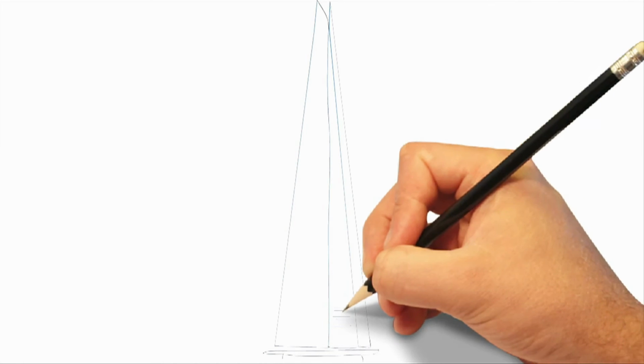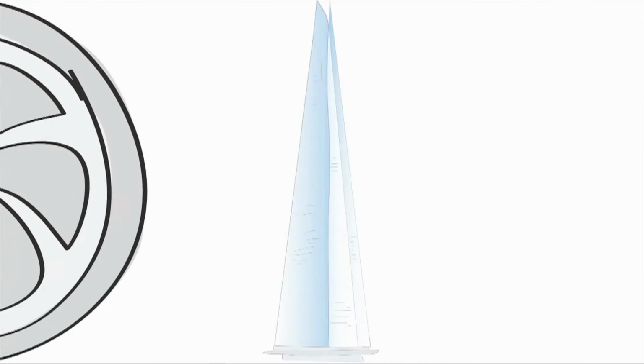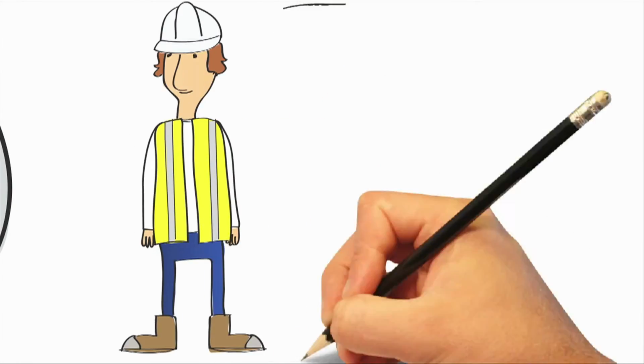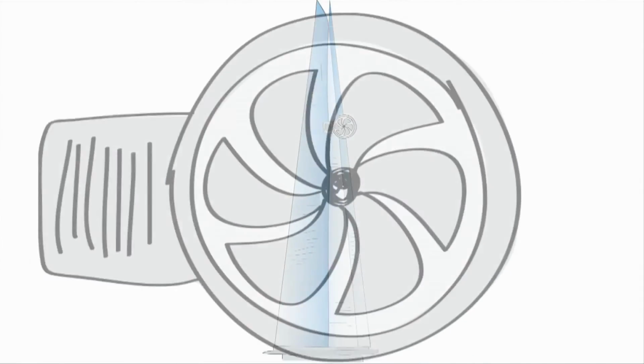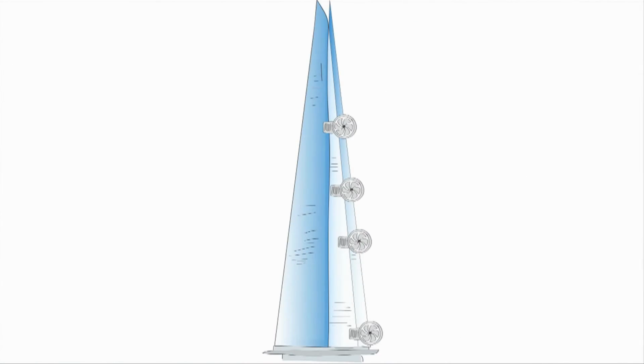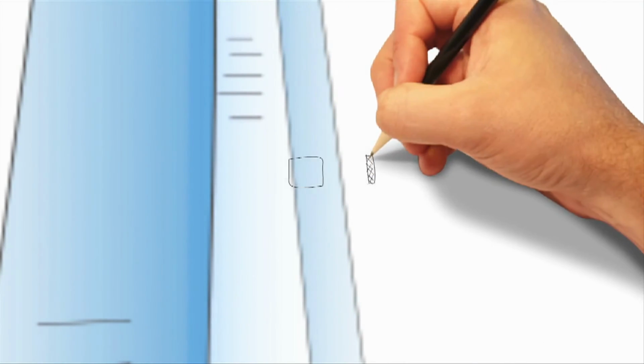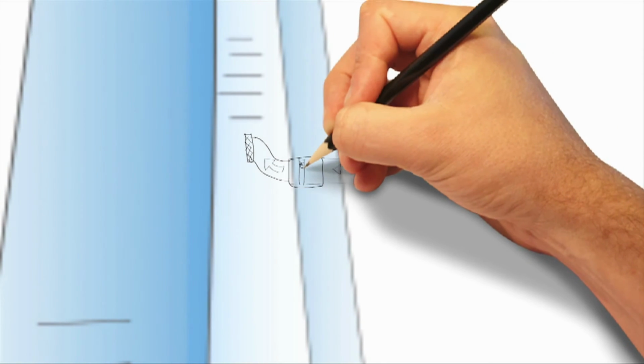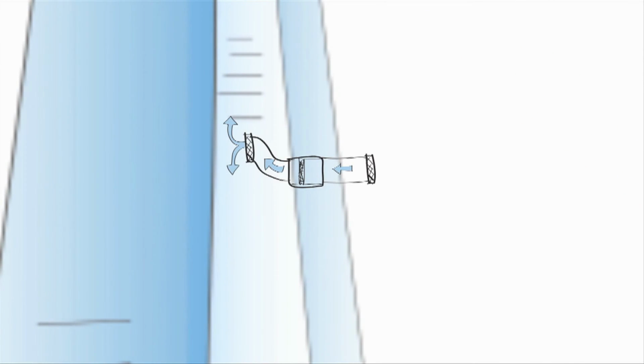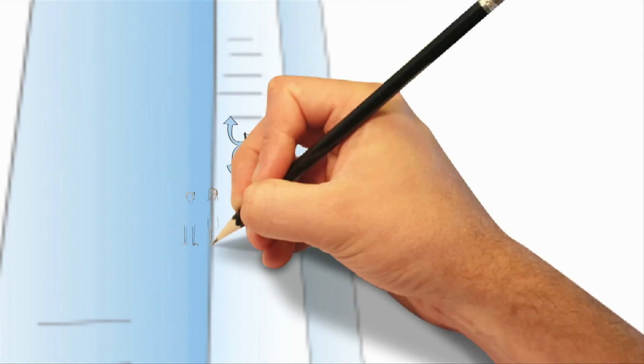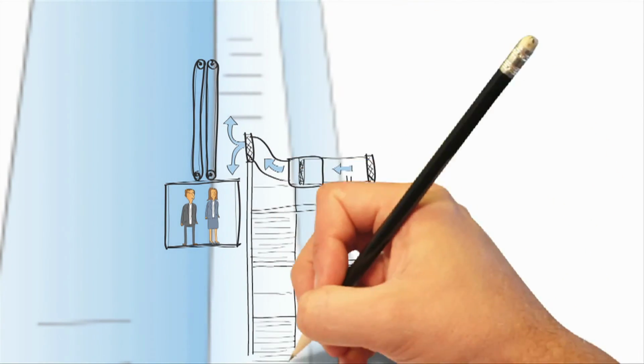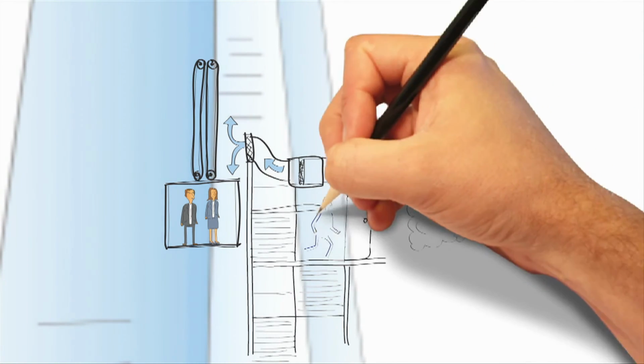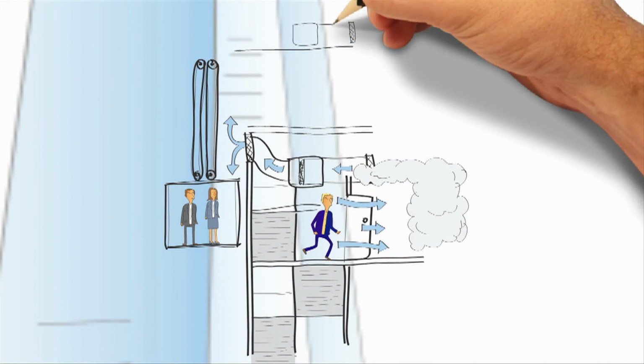Another way that I've helped to ensure the Shard works safely in an evacuation is in the lift and stair pressurisation system. In this system, large fans wider than I am tall are located at each of the equipment levels, and they blow outside air into the lift shaft and escape stairs. This means the lifts and stairs are always under positive air pressure, so when you open a stair or lift door, air comes rushing out. This in turn means that smoke is unable to enter these spaces, and building occupants can safely escape using the lifts and stairs at any time.